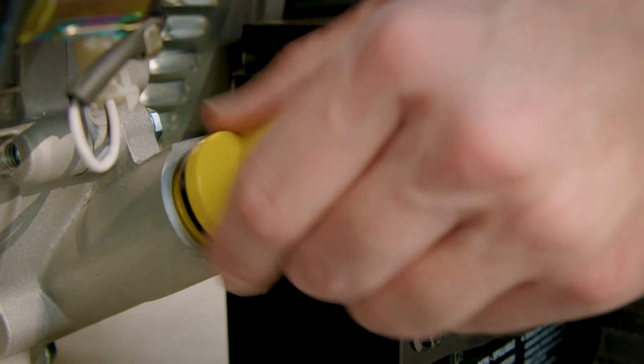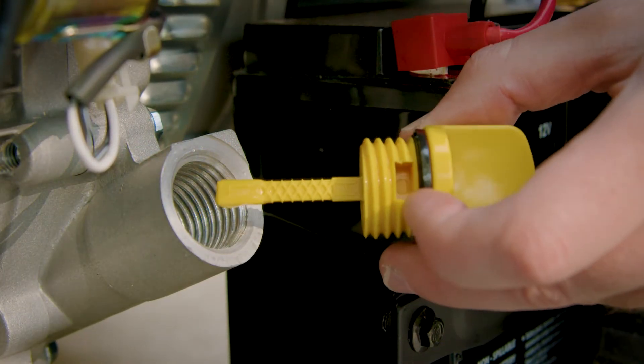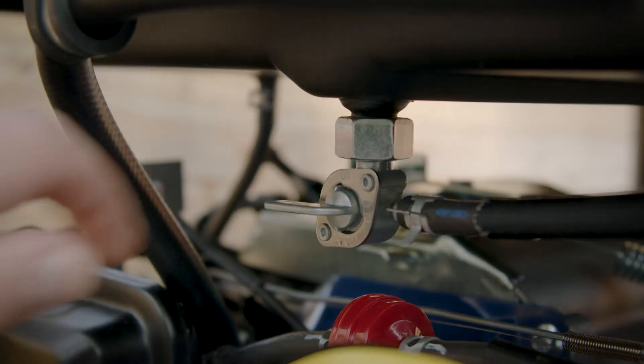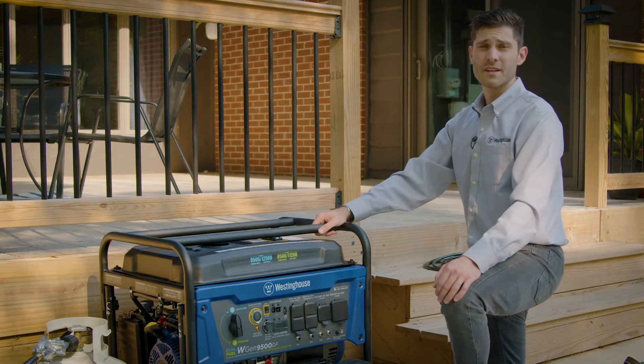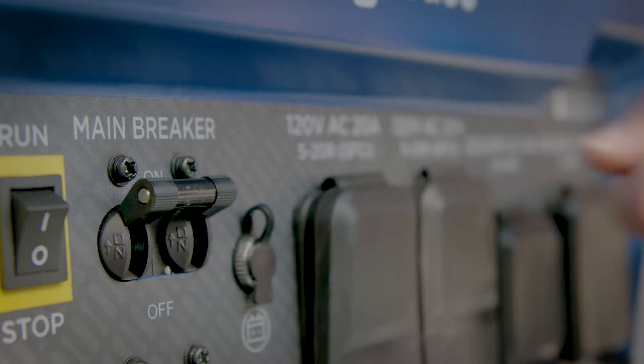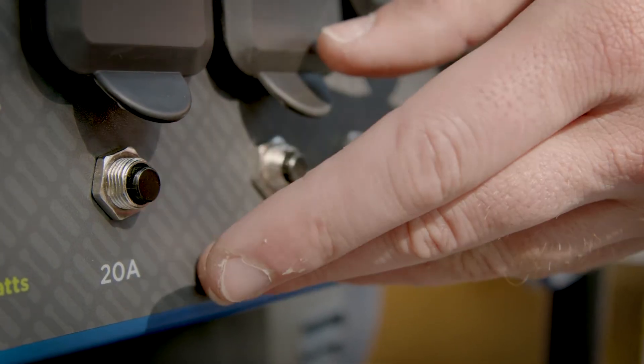Make sure that your generator is in safe operating condition. Check the oil level, make sure you've got plenty of gas, check your battery connection, and turn your fuel switch to the on position. Check that the breakers on your generator and transfer switch are in the operating position. The flip style breakers should be up and the button style breakers pressed in.